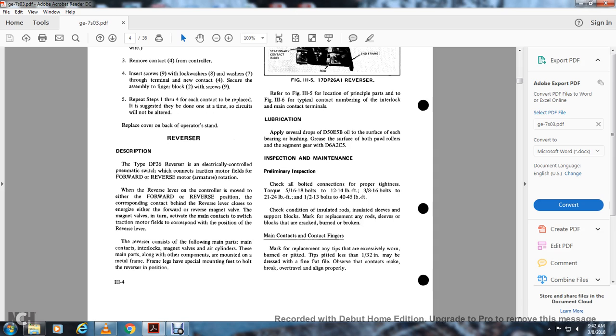Check all the bolted connections for proper tightness. Torque the 5/16-18 thread bolts to 12 to 14 foot-pounds, 3/8-16 thread bolts to 21 to 24 foot-pounds, and 1/2-13 thread bolts to 40 to 45 foot-pounds. Check the condition of insulated rods, insulated sleeves, and support blocks. Mark for replacement any of the rods, sleeves, and bolts that are cracked, burned, or broken.